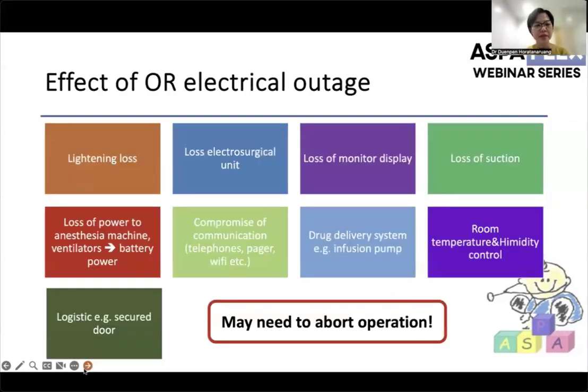The electrical outage could affect different aspects, such as lighting loss: the team will have to work in the dark, especially in flash flood when the generator cannot be used. Also the loss of the electrosurgical unit, so surgeons might have to use different measures to stop bleeding. Also loss of monitor display, loss of suction power, and the anesthesia machine and ventilators have to be on battery power. Communication is compromised because of failure of telephone, pager, or Wi-Fi, and it affects the drug delivery system, such as infusion pumps.